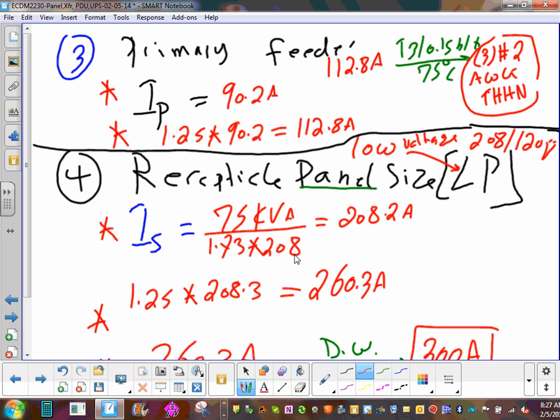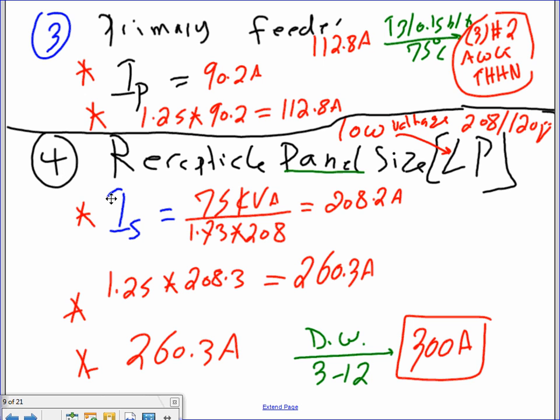The only difference here is we should have first sized the transformer, because the transformer could be different. The reason why we came with the same number here, guys, is because the transformer size was very close to the actual size that we came up with, right? So 300. So we're good with that. All right, so I have 300 amp. Everybody's good with that? 300 amp panel.